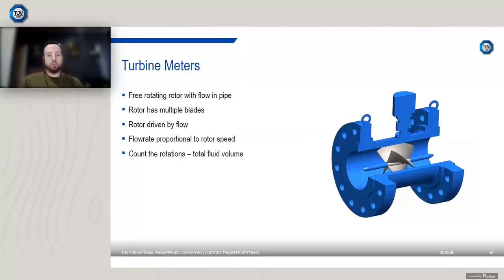The next traditional technology is turbine meters. So how do these work? Well, you've got a free rotating rotor with flow in the pipe. The rotor usually has multiple blades, and the rotation of this rotor is driven by the flow of your fluid. And the flow rate is proportional to the rotor speed. So simply count the rotations and you can determine the total volume that's passed through the meter.